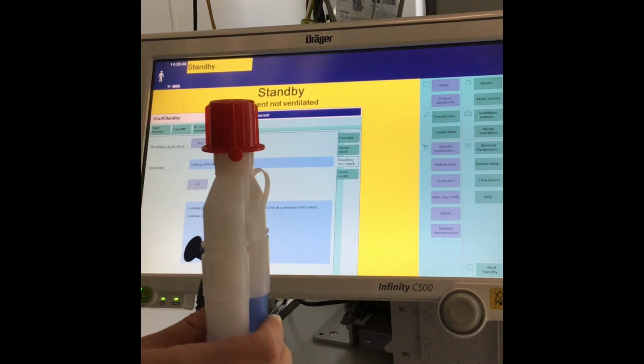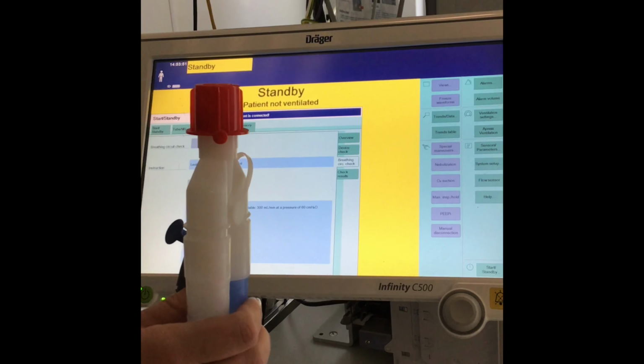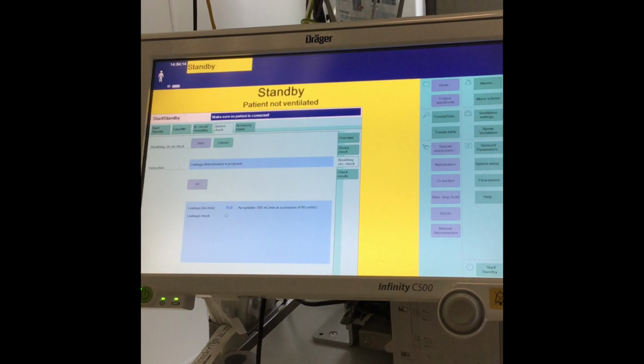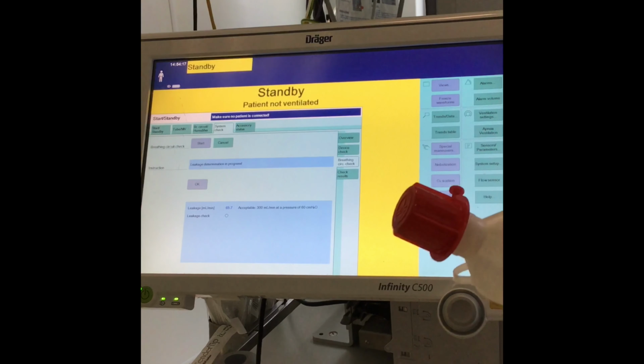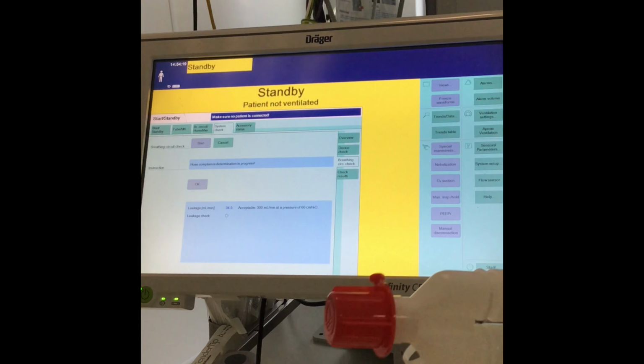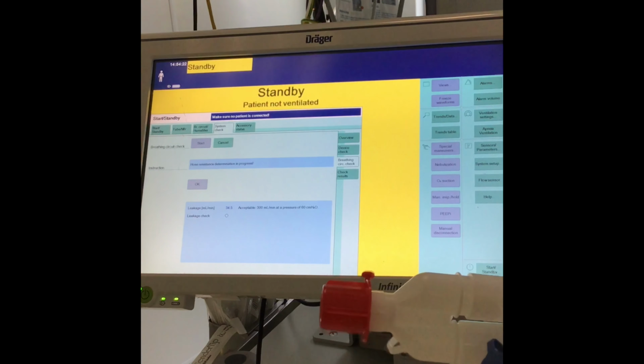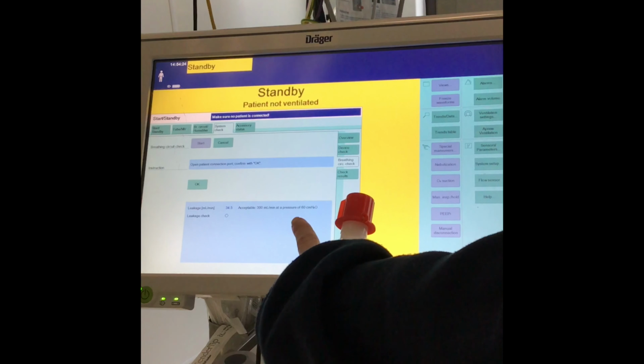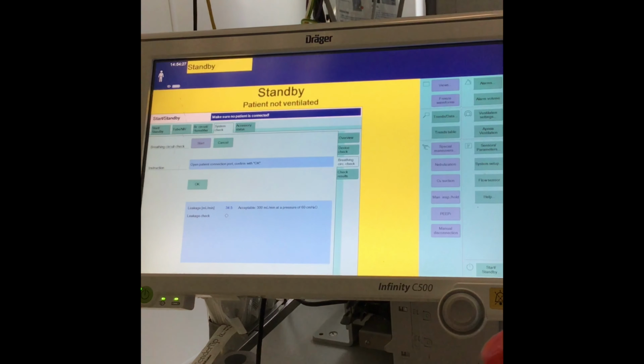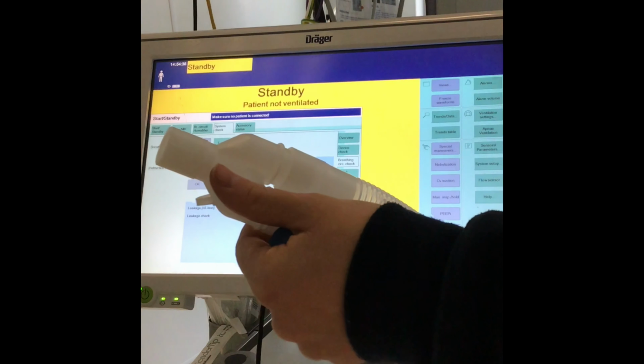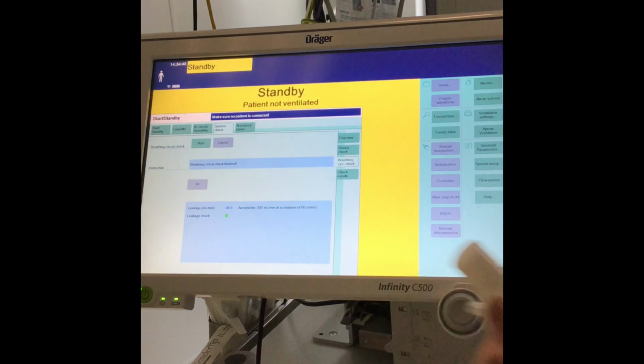And this is just checking that there's no cracks or leaks within the ventilator tubing. This is the point where it will fail if you've connected your water bath to the bag of water already. The acceptable limit is 300 millilitres per minute. Okay, so the next instruction is to open the connection port. We'll just open it up to air and we're going to hit OK. And that's it. And you've got the instruction there that the breathing circuit check is now finished. So that's the ventilator all ready for patient use.